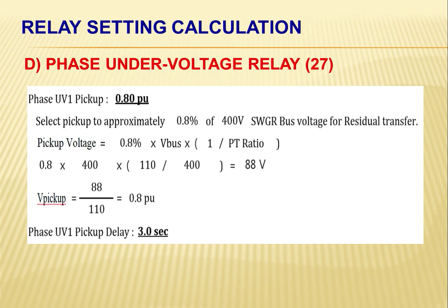Normally, we need to have at least 80% voltage on our buses. Beyond that, the relay will operate and trip the system, or trip the breaker. From here, we'll be using 80% of the 400 volt switchgear bus voltage, so this will be 0.8. This will be multiplied only on the bus voltage times also the 1 over the PT ratio.